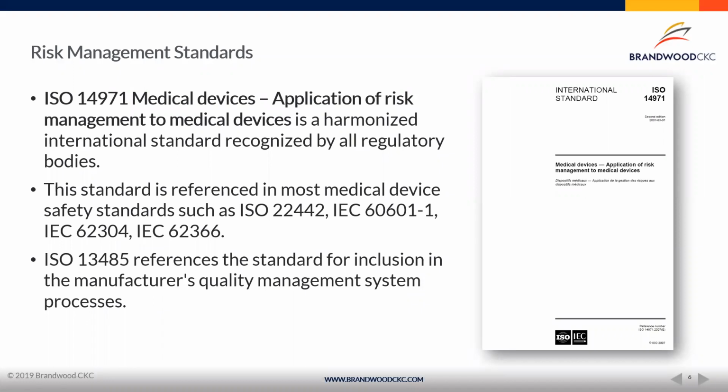I will note ISO 14971 is referenced in a ton of safety standards and other regulatory standards. Anything from ISO 22442, which is the BSE, TSE animal products in medical devices, to electrical safety standards, IEC 60601, software 62304, and usability 62366. So they specifically call out the use and the appropriate nature of the 14971 standard.